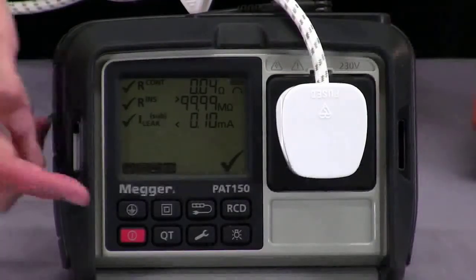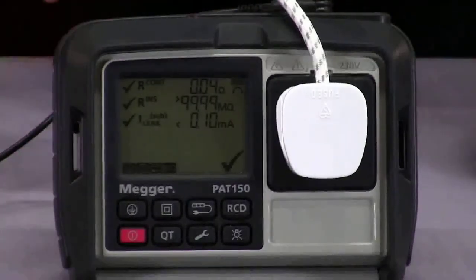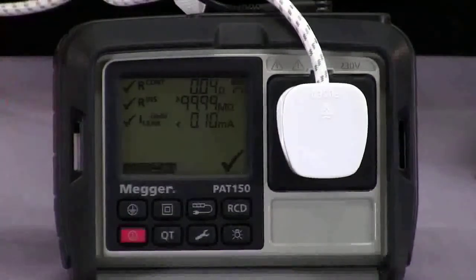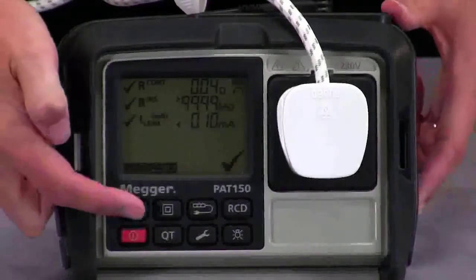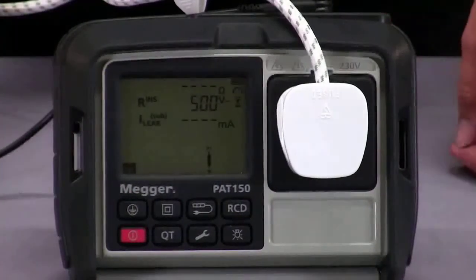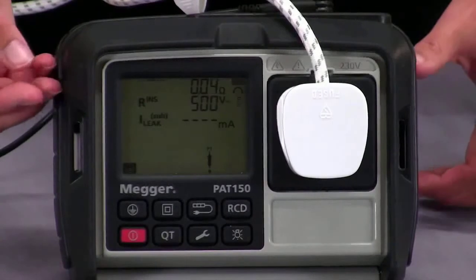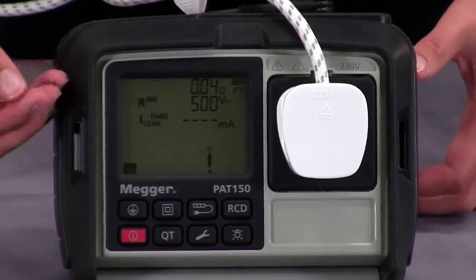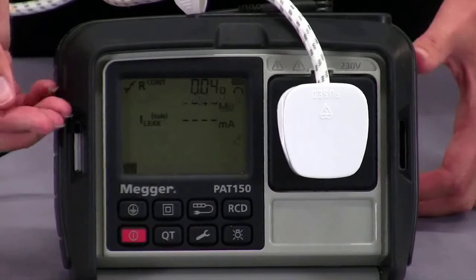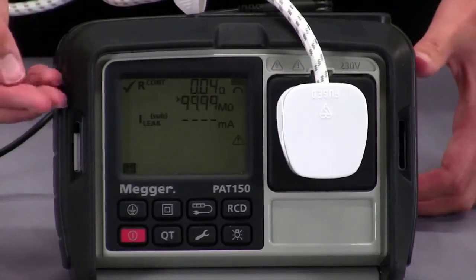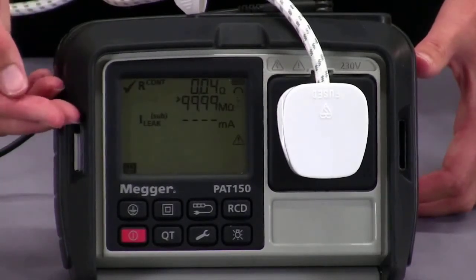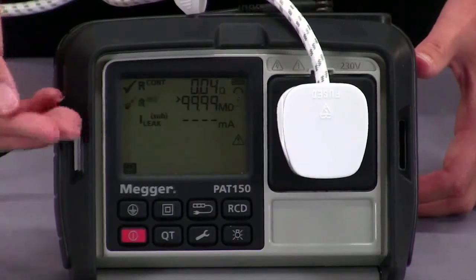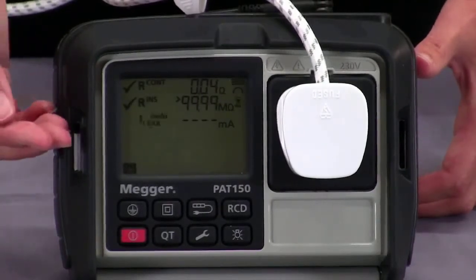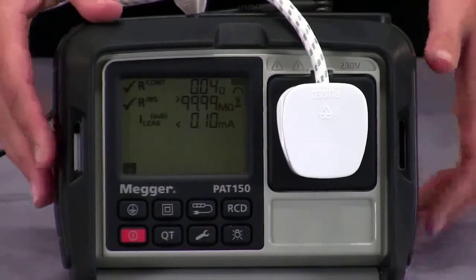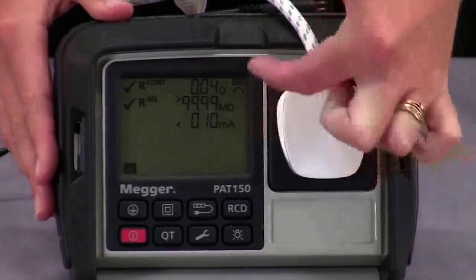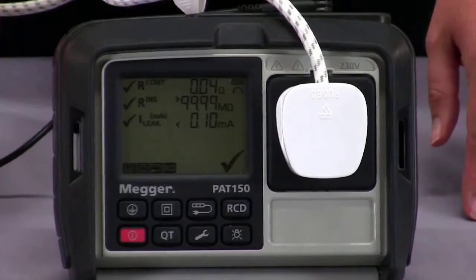I will now demonstrate the Class 1 automated test. I've got my appliance already plugged in along with my earth continuity lead. I can just press my Class 1 button and that will start the test. So it's now performing my 200 milliamp continuity test. It will then move on to my insulation resistance test, which I have set at 500 volts, but if you're testing IT equipment you could change that to 250 volts. It will then move on to my substitute leakage test. At the end of the test you will see whether it's passed or failed, indicated by the tick or the cross on the right hand side.